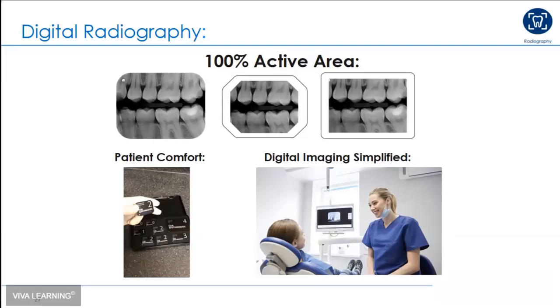So the way that this system works is you expose the films in the treatment room. Let's say you're taking 4 bite wings. You would expose the films in the treatment room. The assistant or the hygienist will take the films, go into the darkroom and take the phosphor plates out of their barrier sleeves and drop them into this phosphor plate transfer box. That transfer box will allow her now to deglove and place these clean films into the processor, in which she can now get an image scan, which will now scan the image.